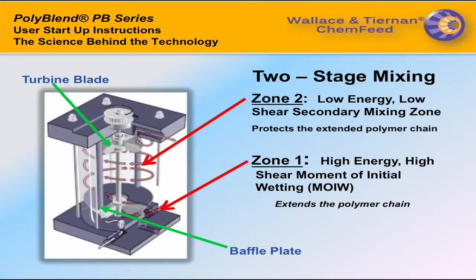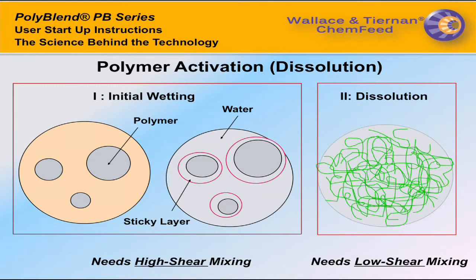All of our polymer blending systems utilize two-stage mixing. The first stage is designed for high energy at the moment of initial wetting. The second stage utilizes lower energy to allow the expanding polymer chain to expose its charge sites without fracturing or damaging the polymer chain. The objective of polymer activation is aimed at getting the most use from the polymers you purchase and use, therefore being more efficient and having lower operating cost.